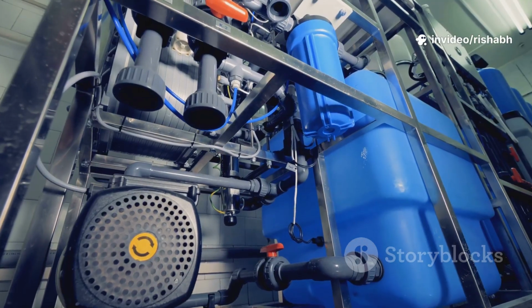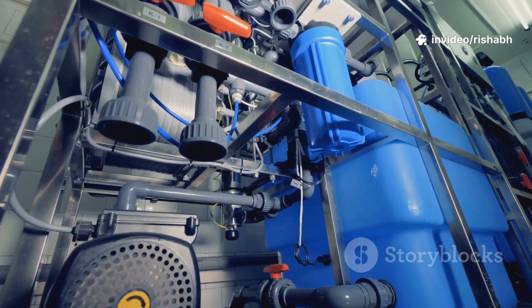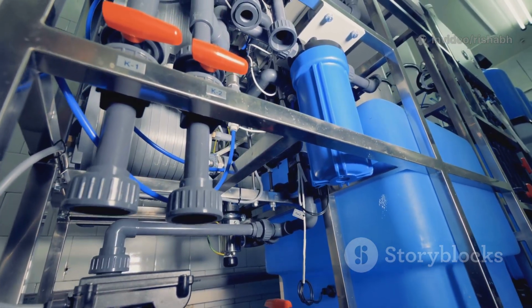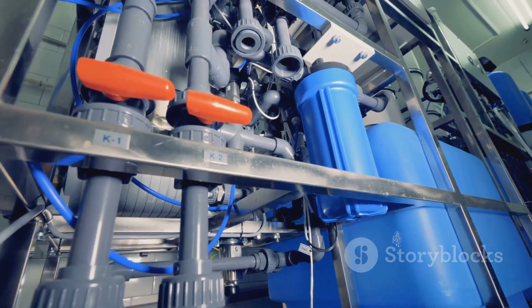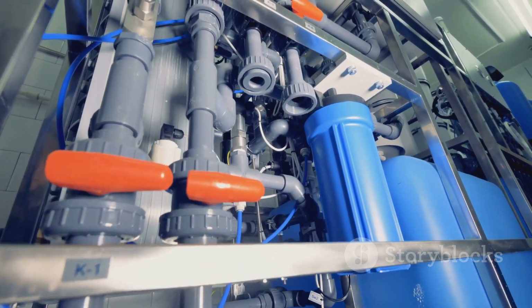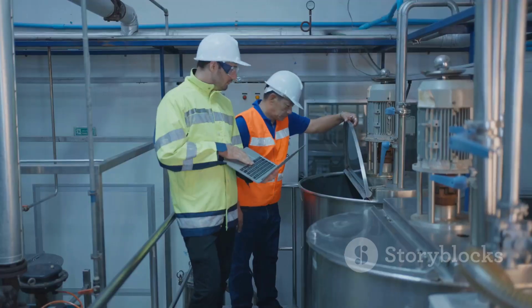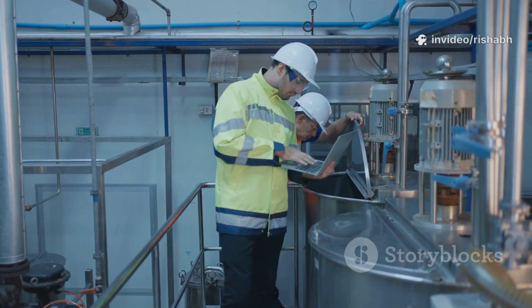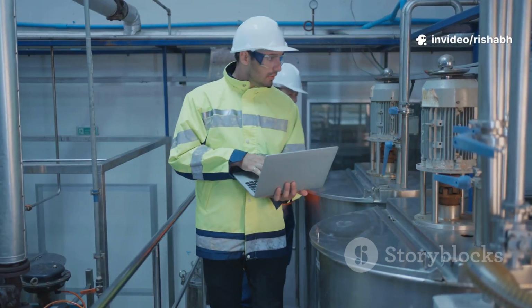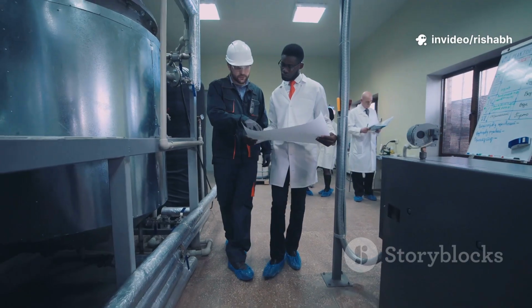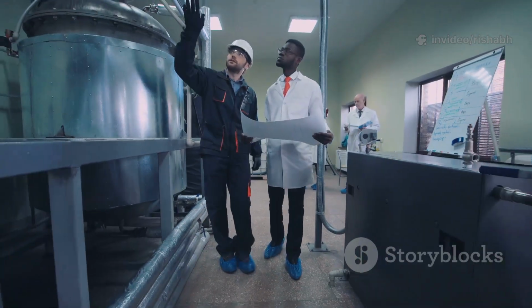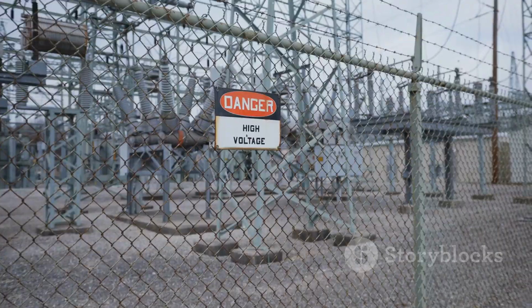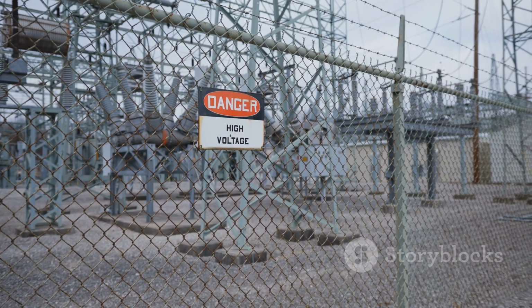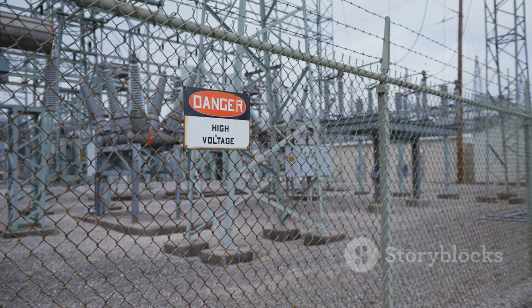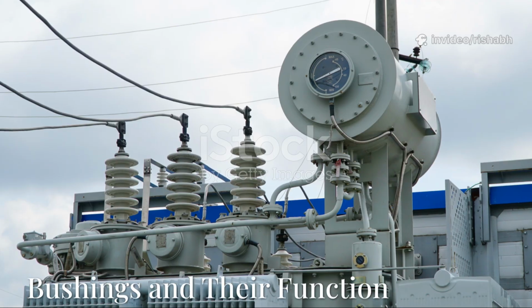The oil itself is purified through a process of filtering, heating, and vacuum treatment to remove dissolved gases, water, and particulate matter. This meticulous preparation ensures the insulation system can withstand the electrical stresses and provide reliable service for many decades. It is a sealed, pristine internal universe designed for high-stress performance.